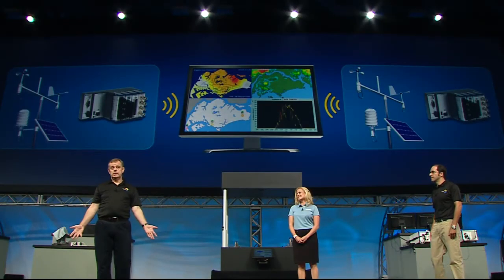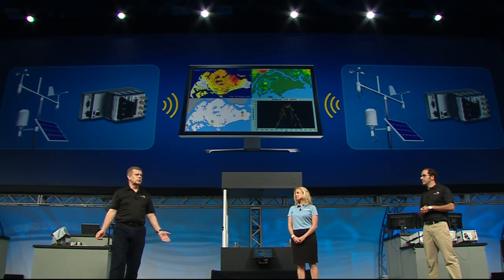Can you tell us about the CompactRIO use? All of our stations use CompactRIO. They take synchronized measurements every second, and we manage to synchronize all our remote stations within plus or minus 150 milliseconds using the 3G network and our own high-precision time server. The ruggedness of CompactRIO makes it the perfect choice for the harsh environmental conditions in Singapore, like high temperatures and very high humidity. For the past two years, we had less than 1% downtime, never caused by any NI components — another reason we use CompactRIO for all our stations.